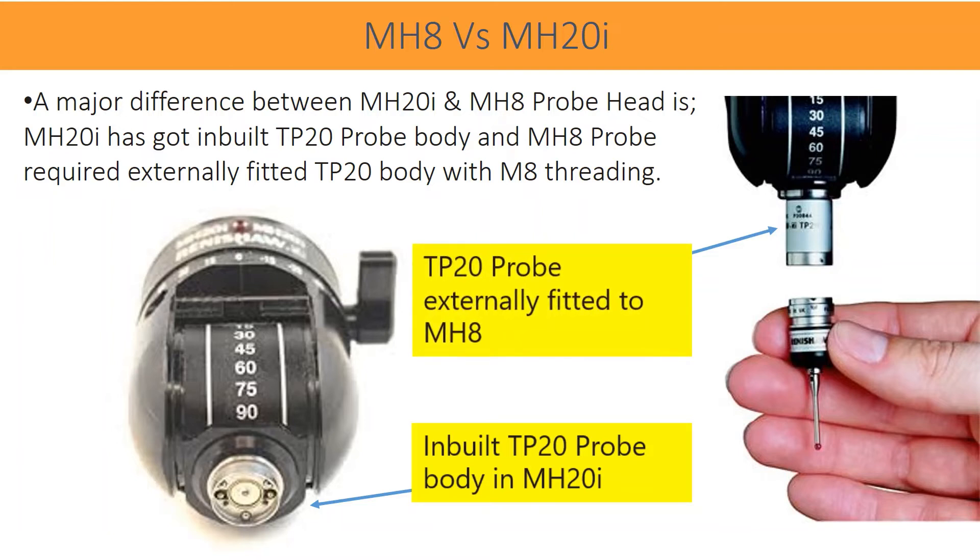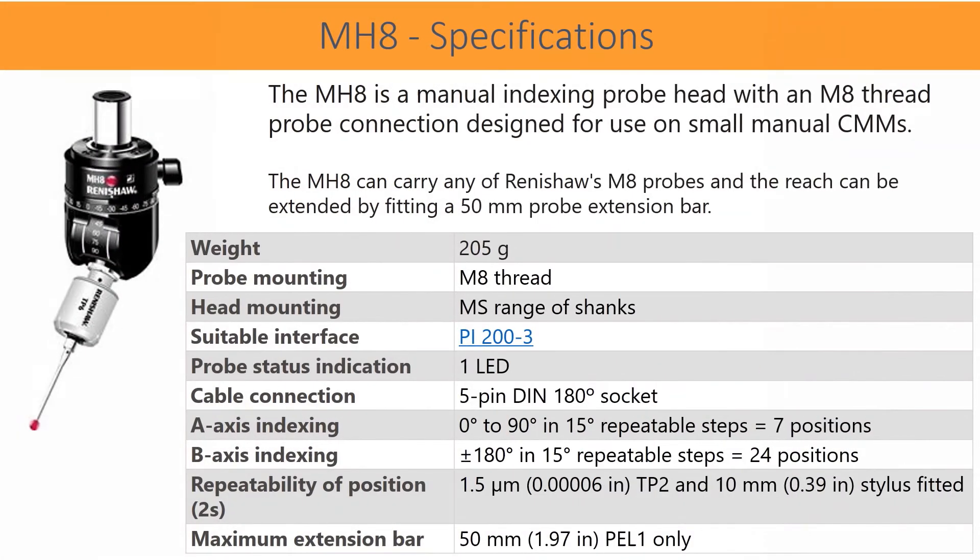A major difference between MH20i and MH8 probe heads: MH20i has an inbuilt TP20 probe body, while MH8 requires an externally fitted TP20 body with M8 threading. A-axis indexing: 0 degrees to 90 degrees in 15-degree repeatable steps, equal to 7 positions. B-axis indexing: ±180 degrees in 15-degree repeatable steps, equal to 24 positions. Repeatability of position: 1.5 µm with TP20 and 10 mm stylus fitted. Maximum extension bar: 50 mm, PEL1 only.